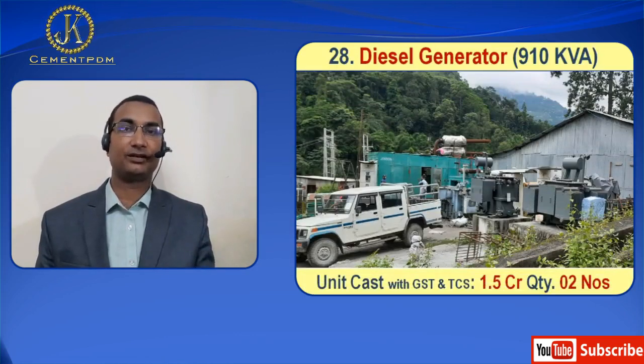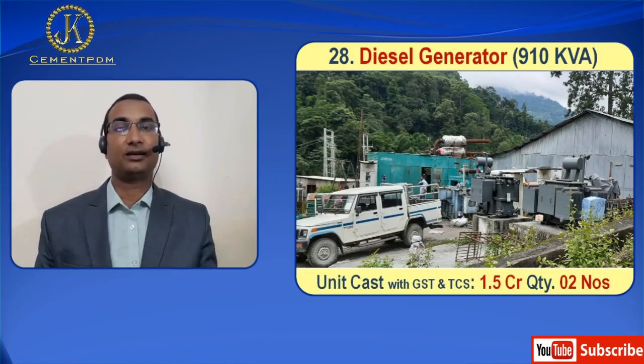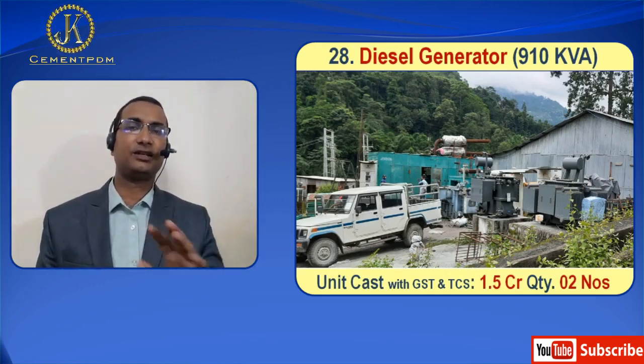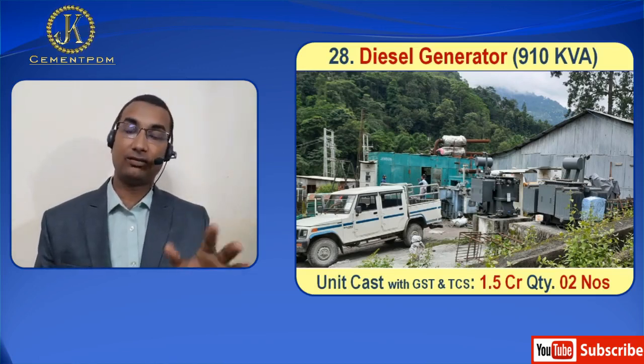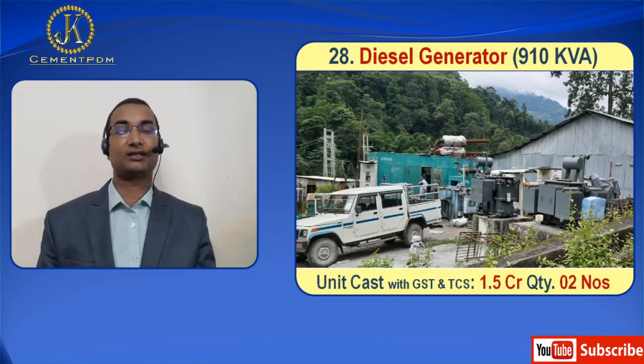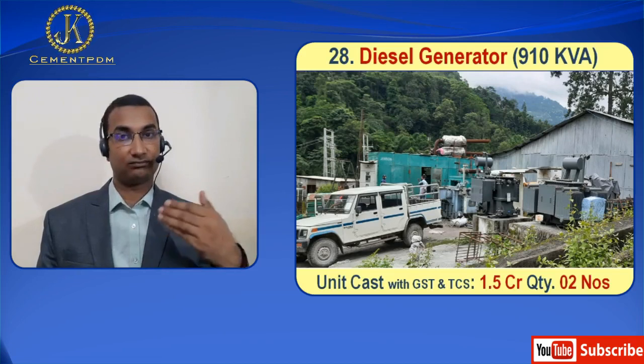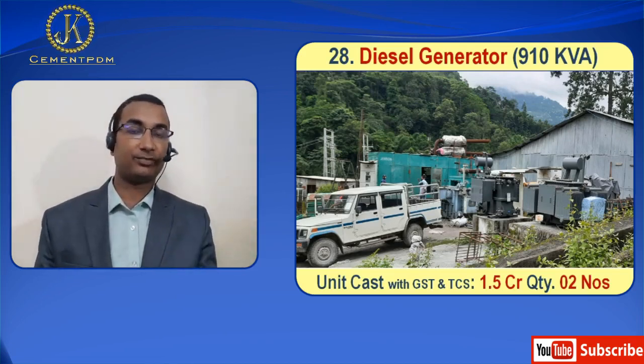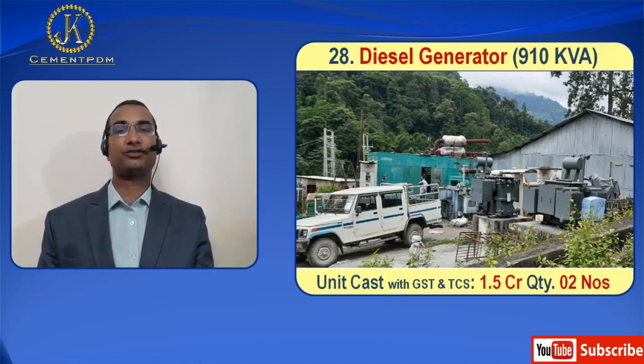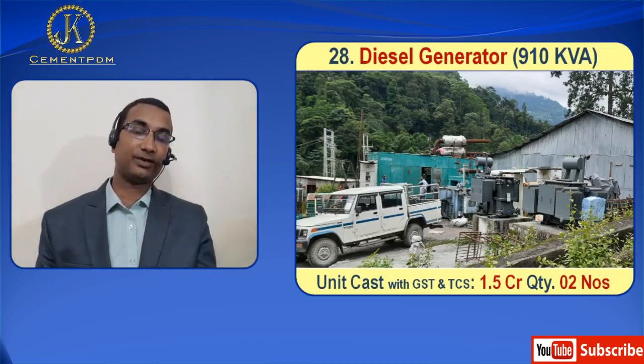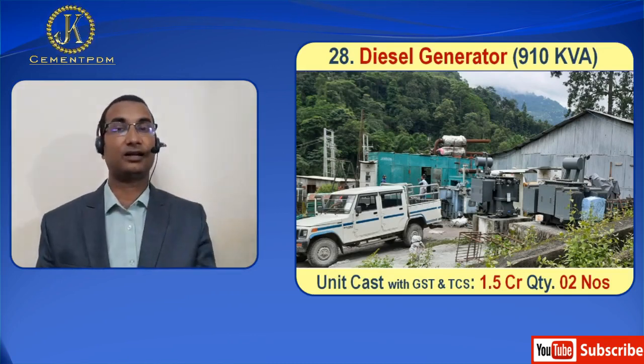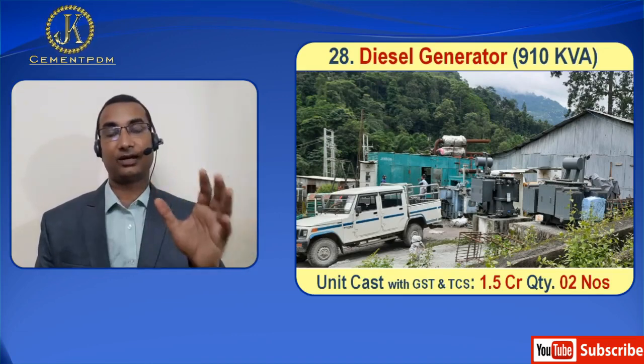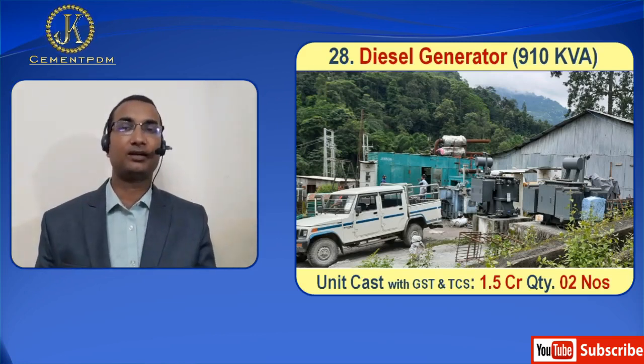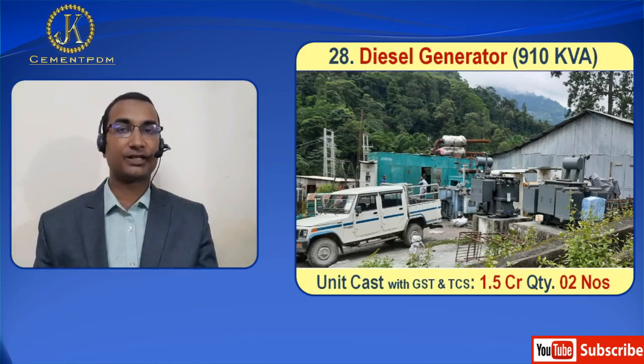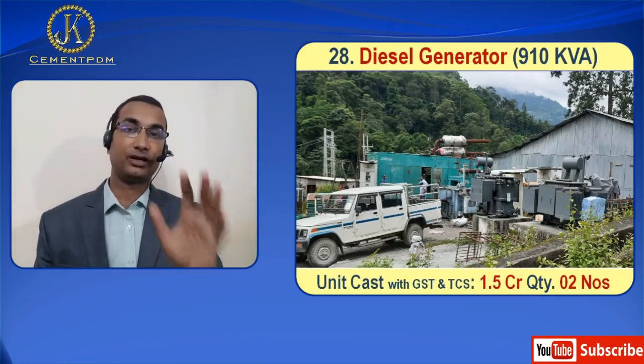You should have a diesel generator. Mostly, in new construction of a hydroelectric project, electricity is not available. In the meantime, you should have minimum 2 number 910 kVA DG available at the site for every activity, because the tunnel boomer works with electricity, the Shotcrete pump inside works with electricity, and dewatering is carried out every time with a dewatering pump. Lighting in the tunnel is also important, and also the blower which gives air in the tunnel. So each and every equipment is working, and on a continuous basis electricity should be available - then you have to have the DG.